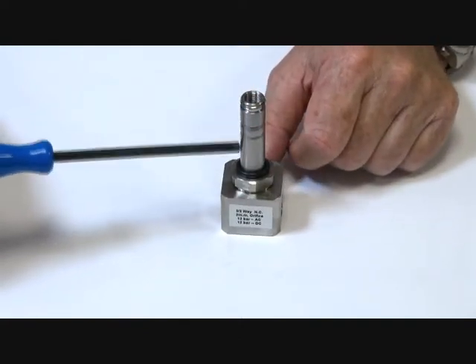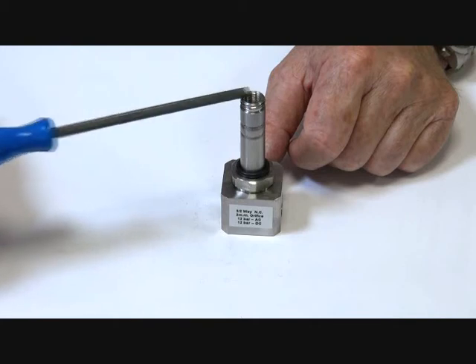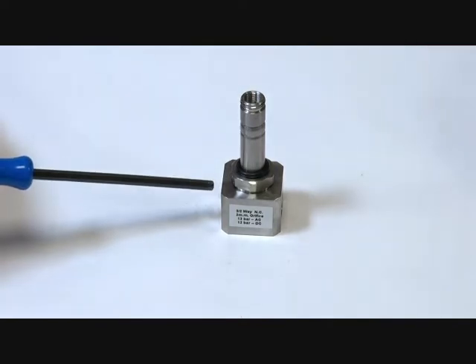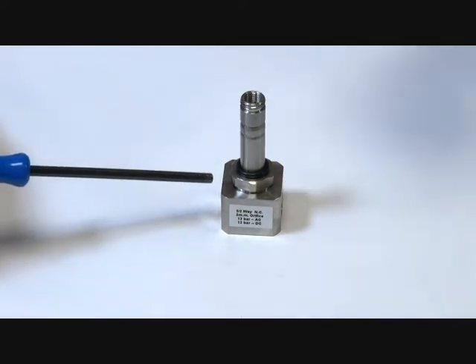When it's energized, the armature comes up, blocks off the top port. You get port 1 and 2 connected, allowing supply through. When de-energized, the downstream exhausts through the top.